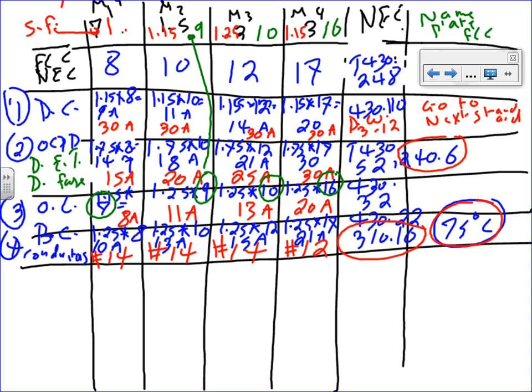Yes, who's raising his hand? I've got a question. I get confused about the terminal ratings. Obviously, you have to go to the lowest one versus the 75, or which one do you rule out? The rules for 310.16: if it's 100 amps or less, you go to 60. Conductor number 1 or less, you go to 60. Other than that, more than 100 amps, more than number 1, you go to 75, no matter what, except if you're dealing with motors. If you're dealing with motors, then you can use 75 all the time. Oh, okay. That's why we're using 75 all the time.